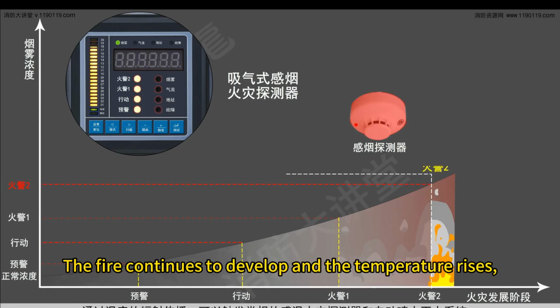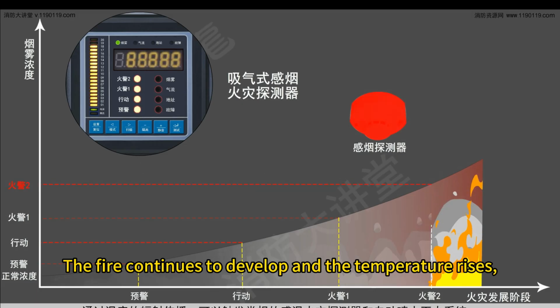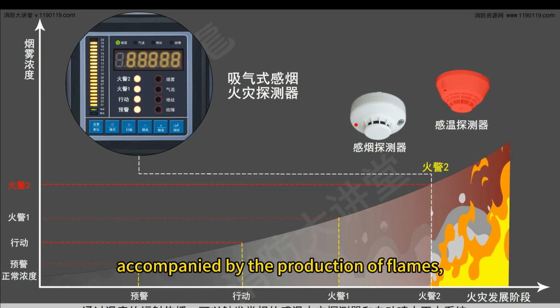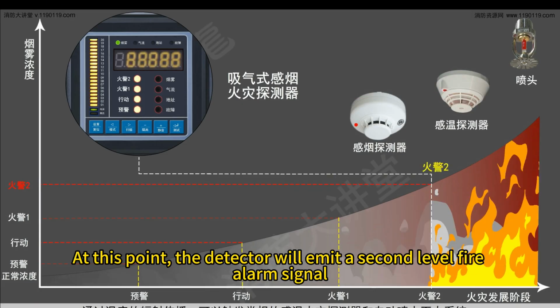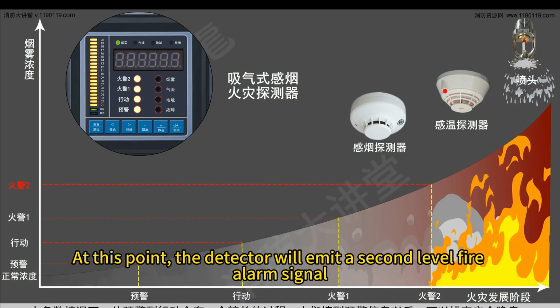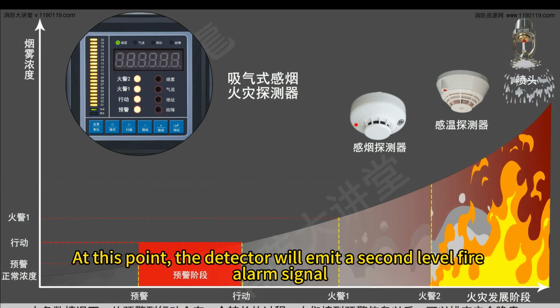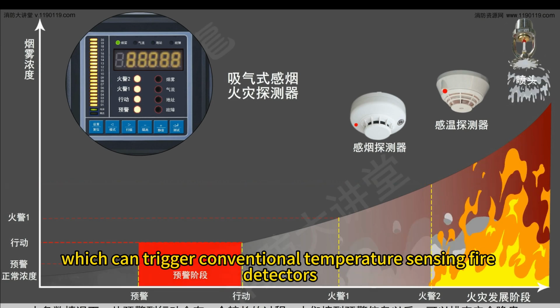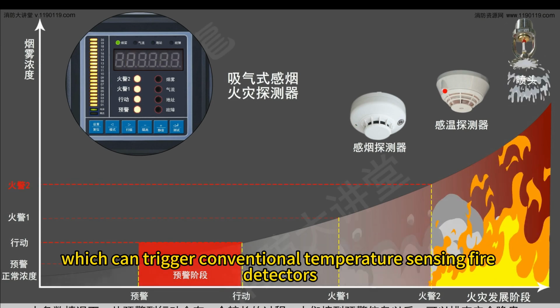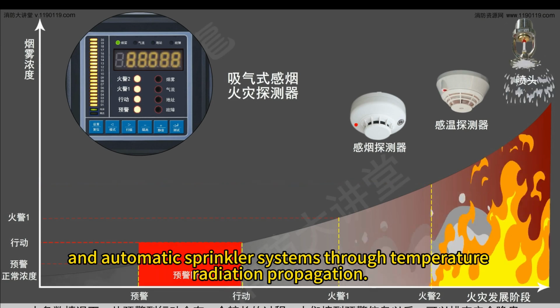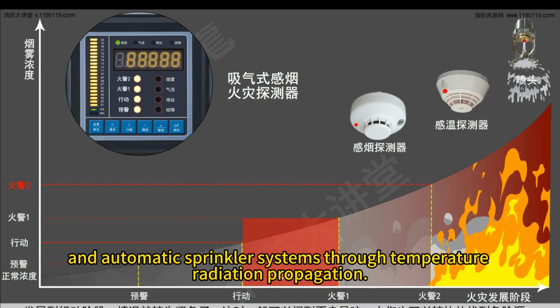The fire continues to develop and the temperature rises, accompanied by the production of flames. At this point, the detector will emit a second-level fire alarm signal, which can trigger conventional temperature-sensing fire detectors and automatic sprinkler systems through temperature radiation propagation.